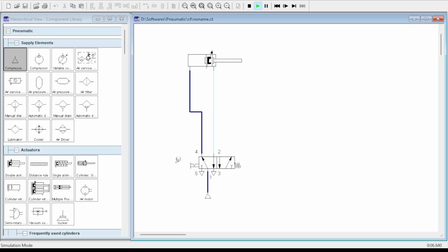For the direct control of a double acting cylinder, the detent switch will be actuated. The air will enter into the cap end to extend it. Similarly, the air will enter into the rod end to retract it. A meter-in circuit is basically a circuit which limits or restricts the air flowing into the cylinder. It can be implemented in two ways. One, by controlling the air entering into the cap end of the cylinder. The other, by controlling the air entering into the rod end of the cylinder.